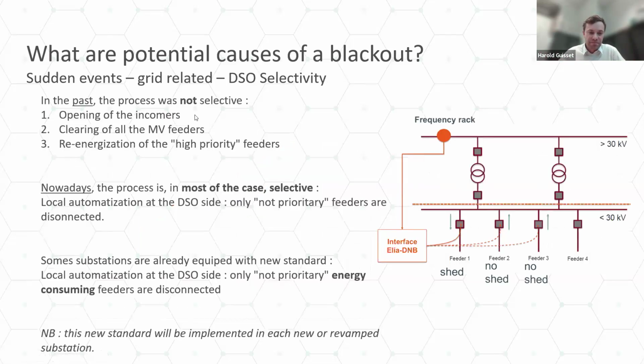Yes, thank you, Harold. So here you can see a single line diagram of a typical substation. You have the high voltage here, then the transformers, and the medium voltage side here with the different feeders. And the way we are doing the load shedding, there is an interface between the TSO and the DSO. So typically in our case, between Elia and RESA, but the same with Ores or Fluvius, Sibelga, and so on in other parts of Belgium. And if the frequency is dropping, I will explain the different steps. We receive via the interface the order to begin the load shedding.